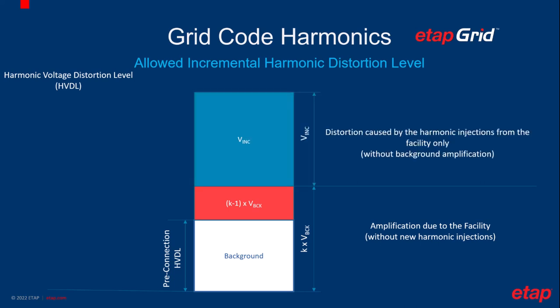The new installation will not only add an impedance, the harmonic sources such as power electronic devices will also introduce new harmonic injections to the power grid. So now we can see the incremental harmonic voltage distortion level caused by the facility is composed of two parts, and the total impact will be compared against the allocated incremental harmonic distortion limits. All the details will be included as part of the final result of this study.